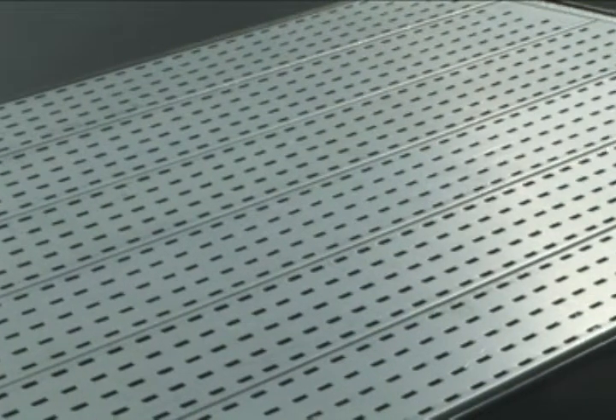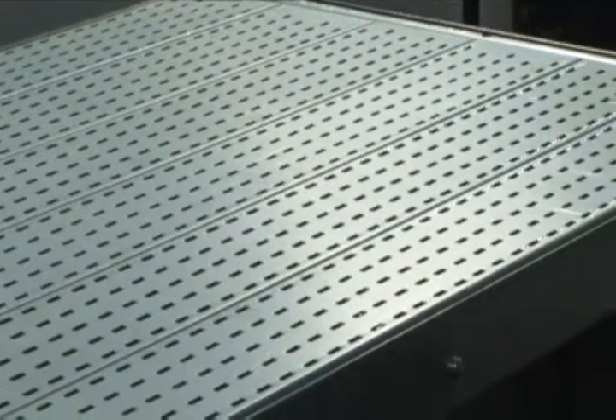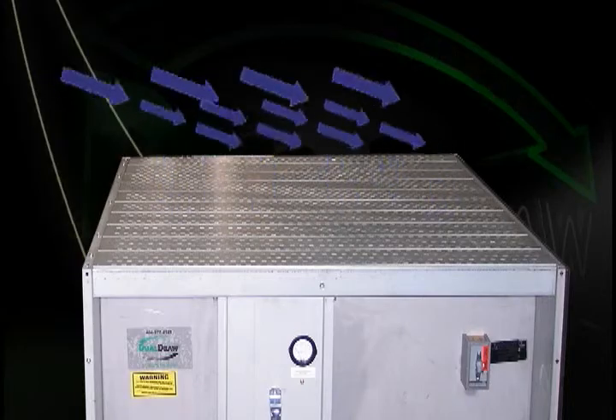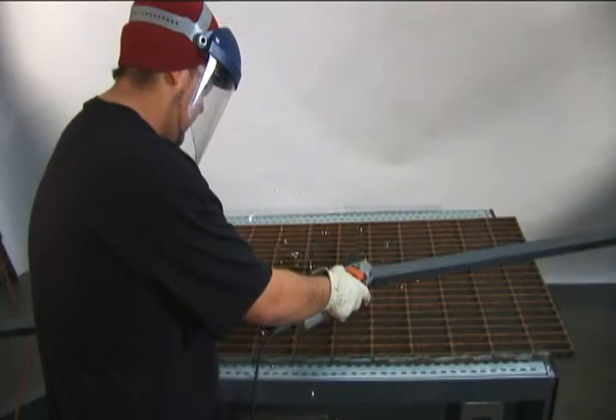These tables utilize the patented dual draw design of an evenly spaced perforated work surface. This design is important because it provides even suction across the work surface and protects the operator no matter where the work is being performed.